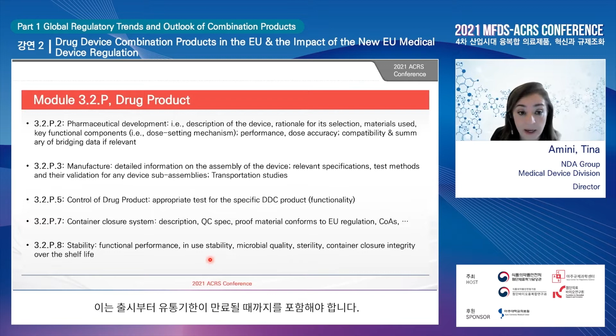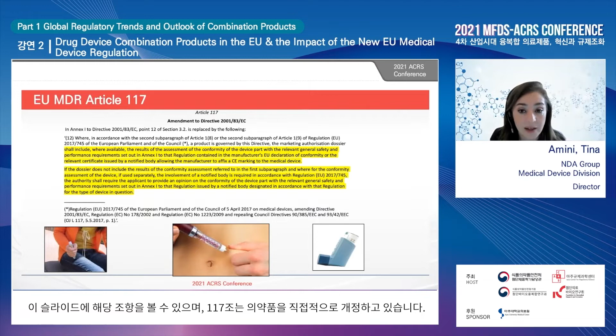So now let's look at the impact of the EU MDR on single integral drug-device combination products. Just a reminder that on 26th of May 2021, the new MDR came into full effect. Article 117 of the MDR is a small article with huge impact. I have put a snapshot of this article on this slide. In brief, Article 117 is amending the Medicinal Product Directive. The marketing authorization application dossier must include an EU certificate issued by a notified body, or it has to include the notified body opinion report if there is no certificate issued by a notified body.